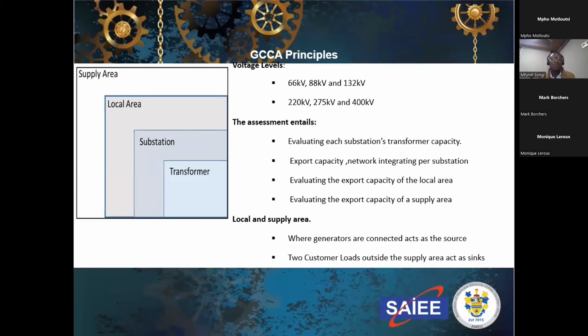Then the assessment looks at the bigger area: the transformer evaluating area, the substation, which would have several transformers. Do we have capacity? Do we have the export capacity, not only of the transformers, but of the lines? Do we have the integration capacity of the substation, and between the transformers, the lines, and the next substation, between provinces? And what is the net export capacity for a local area?